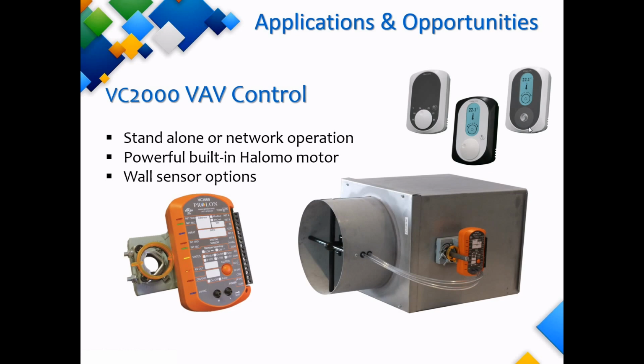Now the T1000 is more than a simple wall sensor. You can access its digital menu and change any parameters on the VC2000 controller. So whether it be for configuring the outputs, the damper, flow settings, everything on the VAV controller can be configured from the T1000 wall sensor.